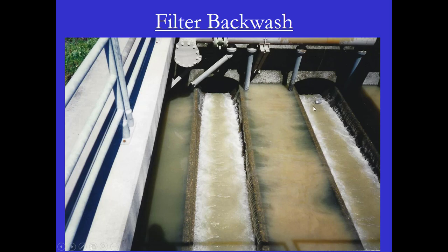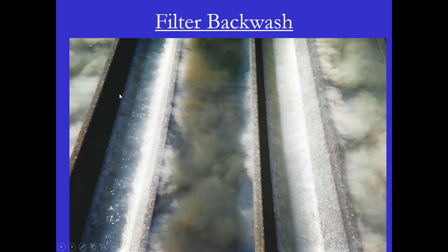While you're collecting samples, you also want to carefully watch the backwash to see if the flow over the troughs is even, and how cloudy and dirty the water is — are some areas of the filter really dirty and some very clean? In this picture, you have a pretty good flow over the wash water trough here, but here there's no flow at all, which is an indication of a problem.